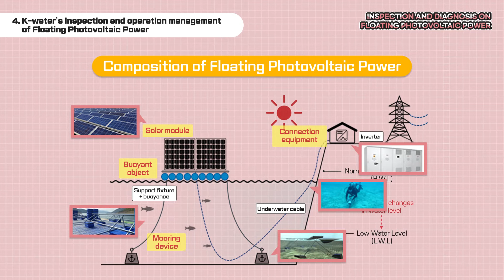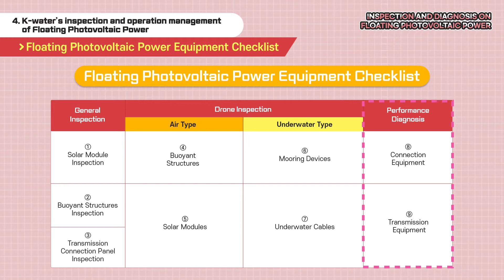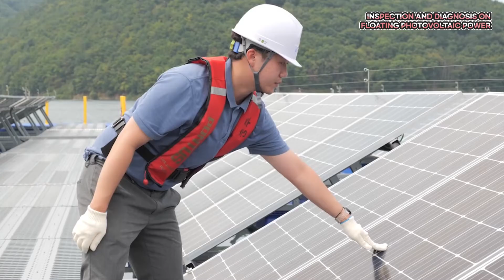The inspection stage for a floating photovoltaic power generation facility is divided into general inspection to check for damages, contamination, and connection conditions at the site, drone inspection to check for twisting of structures with large areas, deterioration of the solar modules, abnormalities of the elastic mooring devices and underwater cables in the air and underwater, and finally performance diagnosis to determine the efficiency of the solar modules and overheating of the connection.